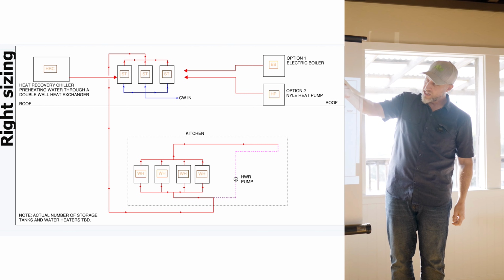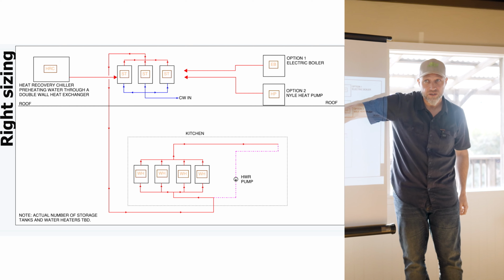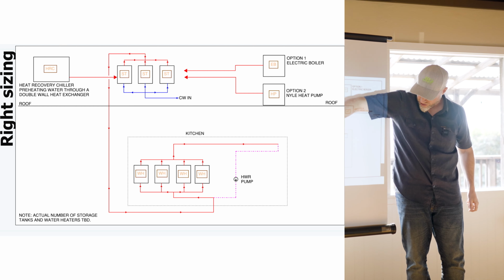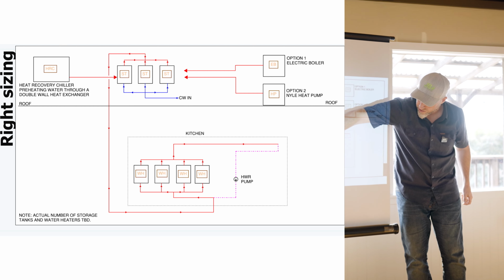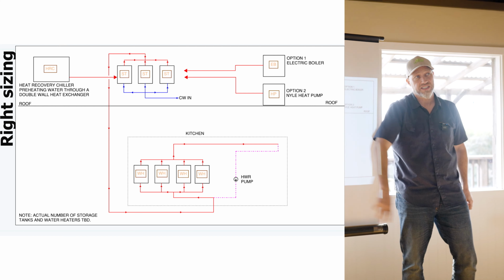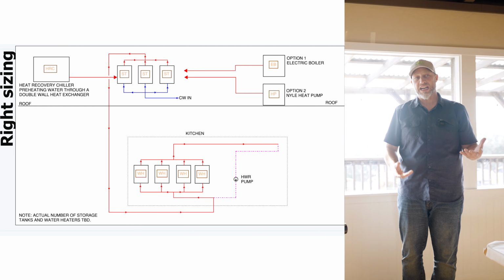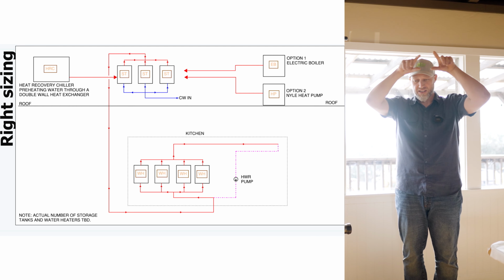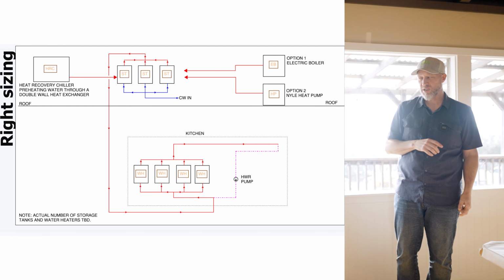We've got backup, send the primary down to a bunch of A.O. Smiths in the kitchen, set up a recirc loop down there, so you're closer to the load, a lot less losses. That's one way to look at it: you've got a big building that doesn't have circ, which is pretty bad.